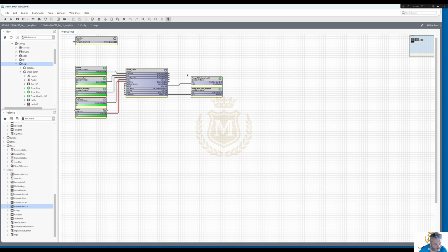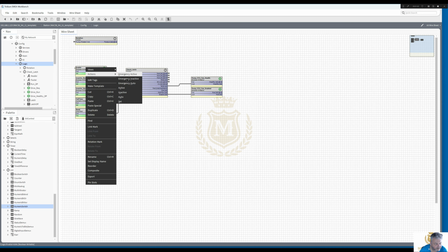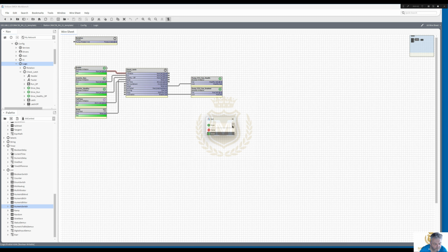So as you can see at the moment, the fan coil or the pump, whatever you want, is healthy and we're enabled. So if I just take it off the enable, so action set, and I'll put it to false, you can see that the unit pump, let's call it a pump, the pump is false. It's still healthy, but we've got a manual run there. See, it's saying manual run here in the mode.